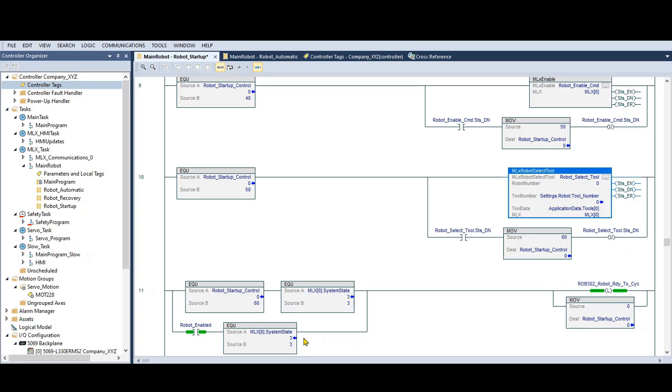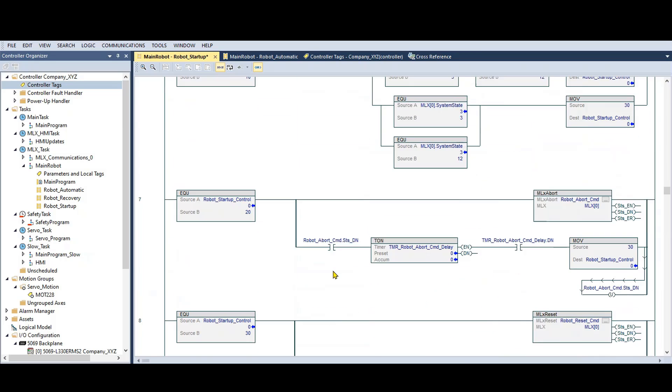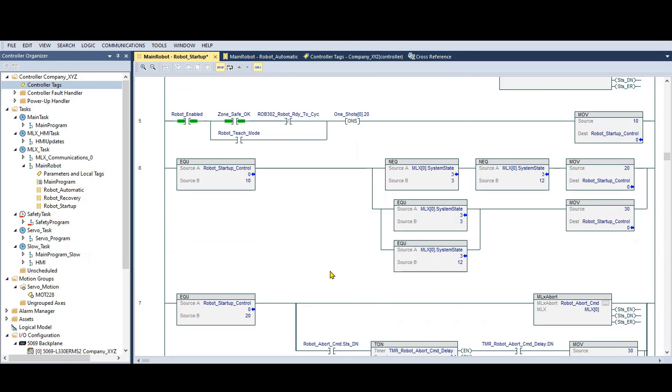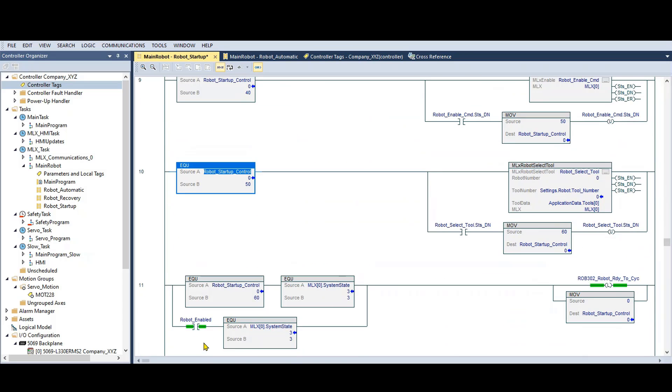However, if you look at the lower branch on the left side of this rung, it's checking for the robot enable tag and the system state equal to idle. If you scroll up, you can see that the robot enable tag had to be on to initiate the startup sequence. Therefore, as soon as the system state is idle, or servo power is on, the robot ready to cycle tag gets latched and the startup step gets set to zero.